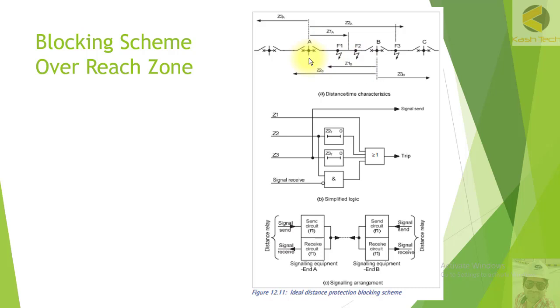Station B will also see the fault in zone 1 in the forward direction. In this case, the relay at station A will pick up and wait for any blocking signal — for example, you can set a timer of 400 milliseconds. Since the fault is in the forward direction, the relay at station B will not send a blocking signal, and the relay will trip within the set time, which is always less than the zone 2 time — very fast.